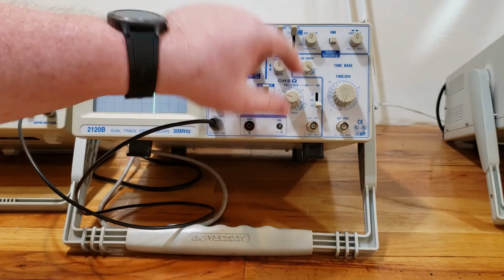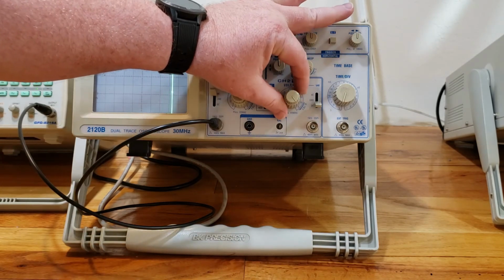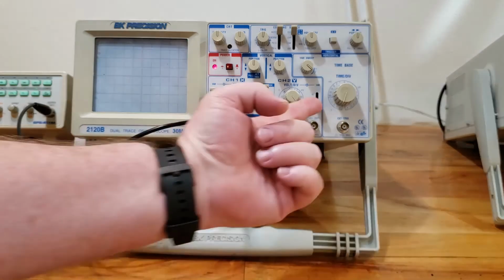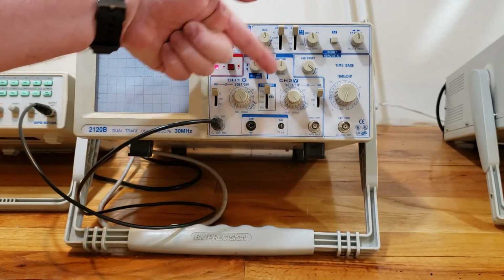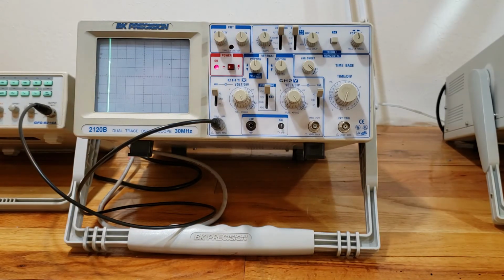The vertical mode switch goes to the upmost position to channel 1. The volt division knob for channel 2: again, 3 things. Top part pushed in, locked into position all the way to the right, volt division set to 0.2 volts. The 3-position switch for channel 2, all the way up to AC, so that all 5 switches should be in the upmost position.